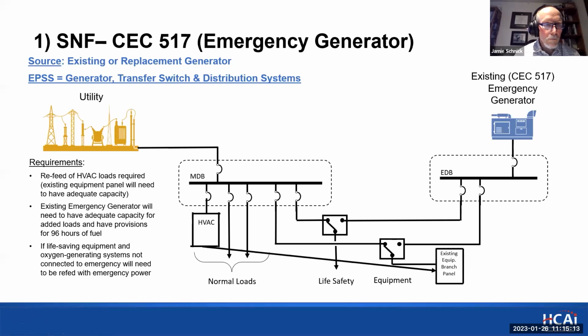These are typically larger mechanical loads, and typically they're connected to, I'm showing the main distribution bus. This is the normal distribution board that's fed by the utility. And typically, in order to bring it into compliance, you need to transfer that to be backed up by the existing generator. A couple things that are required. There needs to be capacity on the existing generator to accept the new loads. That would be done by load studies. And there would be recircuiting for HVAC to get from the normal side to the emergency side.